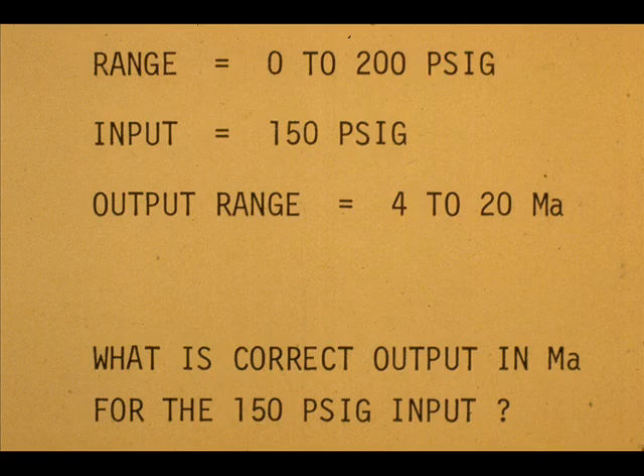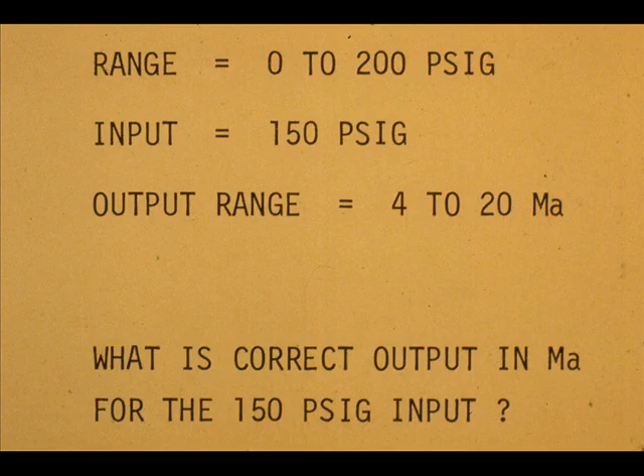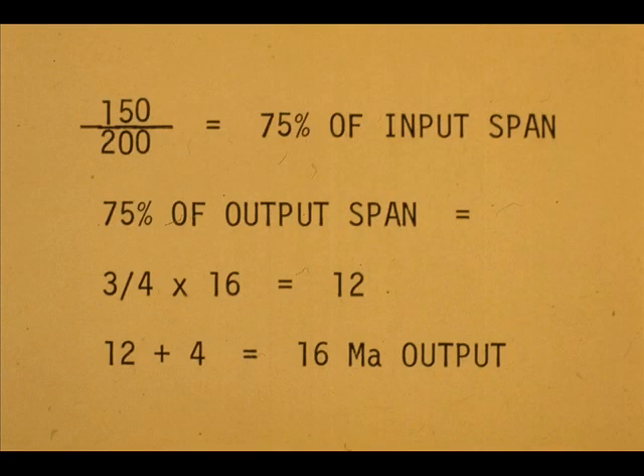By the same reasoning, the correct readout for 100 PSI input to the 0 to 200 PSIG transmitter is 12 milliamps. Here is a problem for you to work. Your answer should be 16 milliamps.